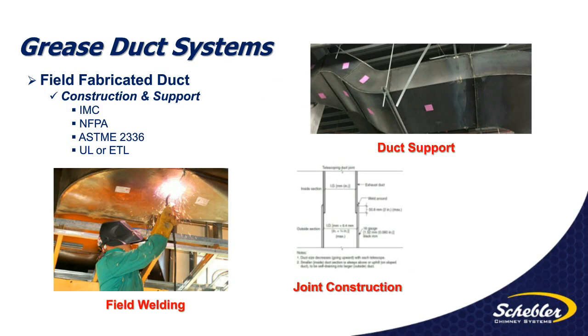Okay, as we covered earlier, if I'm going to assemble or construct a grease duct system in the field, I'm going to need to refer to all the codes and standards above to ensure that I'm providing a safe system. So again, International Mechanical Code, NFPA, ASTM E2336, and/or per the installation manufacturer's instructions, the UL or ETL instructions that are part of it. So field welding of ductwork, joint construction to be compliant with that, and structures and support would be included with that.